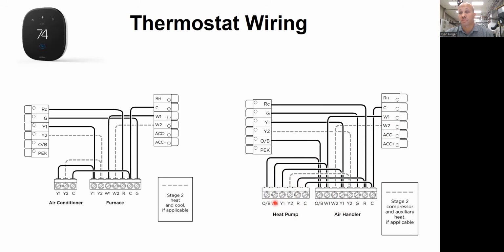But also the heat pump could turn on an electric heater, specifically when the heat pump goes into defrost mode. Remember from last week, when it goes into defrost mode, it really runs cooling in order to thaw the coil outside. That's great. It thawed my coil. Perfect. But it also means I'm blowing cold air inside for a building that wants heat. Not perfect. So when this heat pump goes into defrost mode to thaw its coil, it tells the indoor electric resistance heater, hey, dude, I'm going into defrost. You need to kick on so these people don't get a bunch of cold air blowing at them. We're a team here, man. You got to help me out. So I need that extra wire.